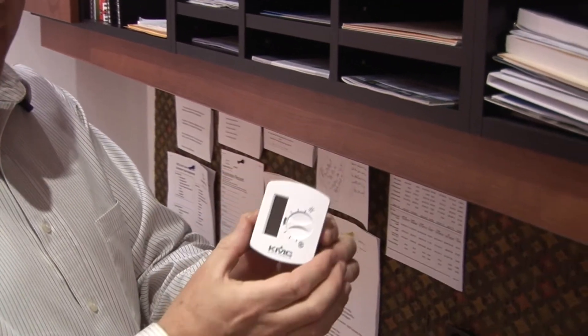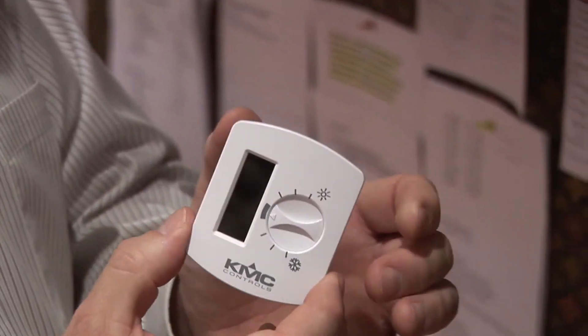In addition to that, the temperature sensor in this room is wireless. It's measuring temperature and has a setpoint adjust so the occupant can decide their own temperature. It receives its power from a solar strip on the side, and once charged it's good for about seven days in darkness. The old concept of sticking the temperature sensor on the wall by the door because that was the easiest place to wire might not hold true anymore — you might want the sensor on your desk, where you actually want to measure 70 degrees.